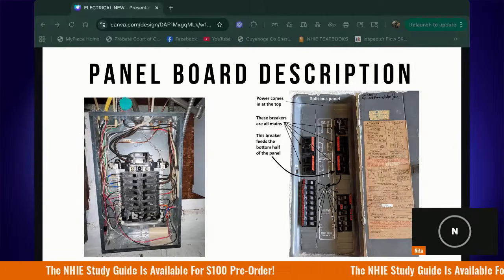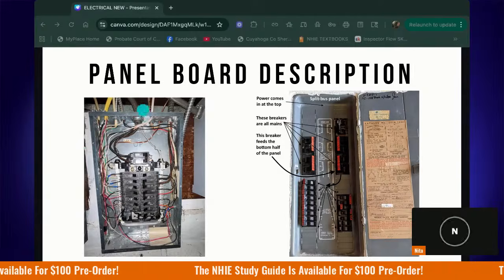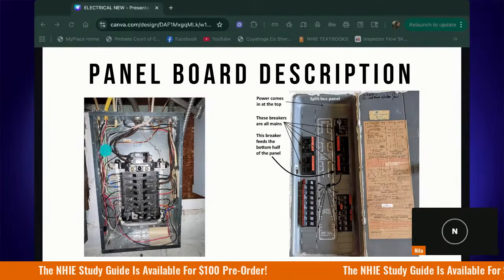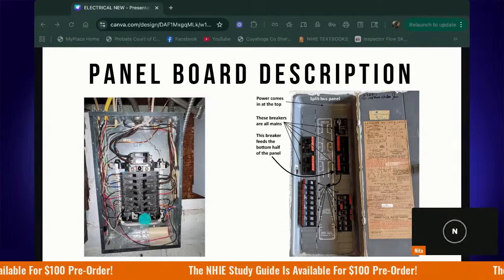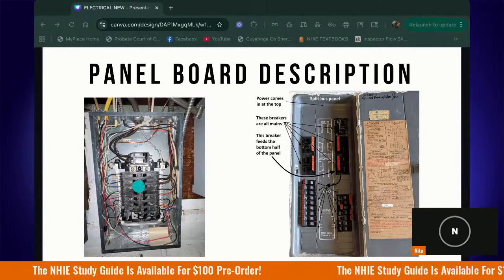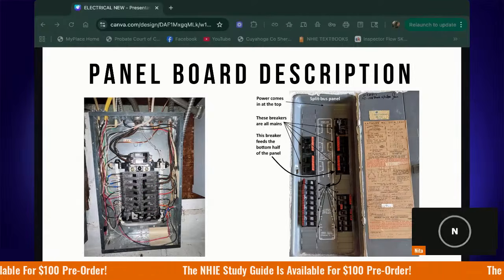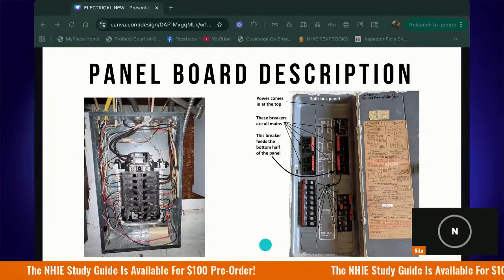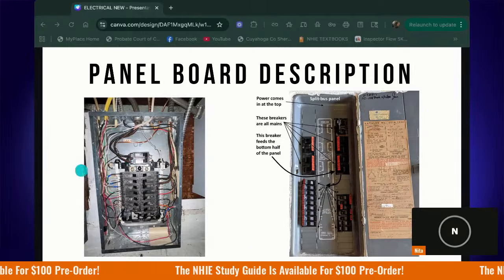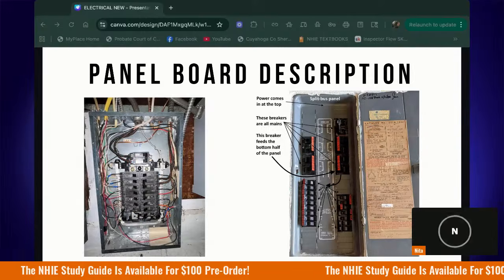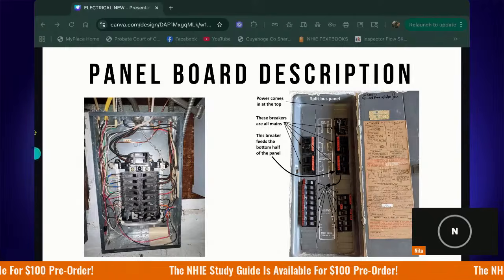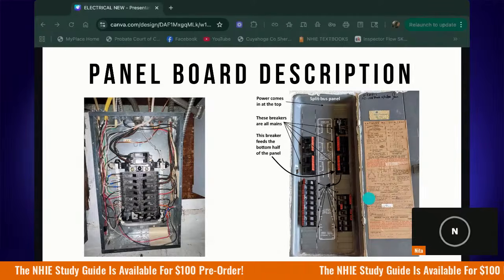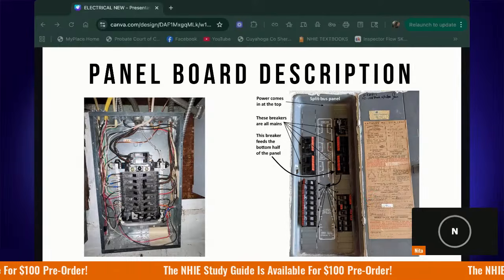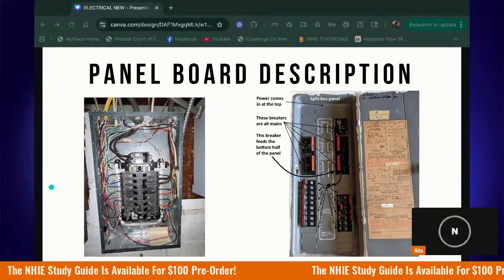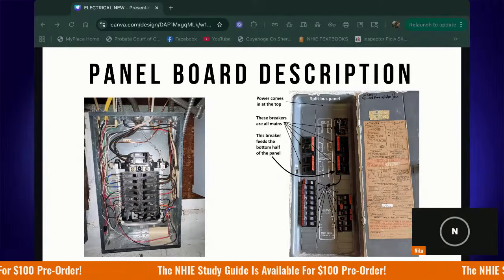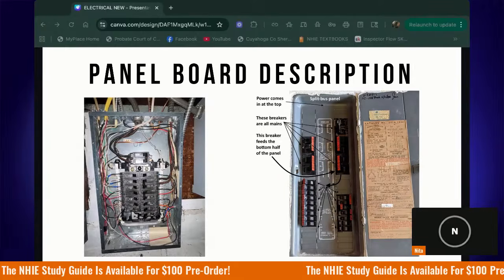So with the main breaker, you have your power flowing through. So this is our 2 hots and a neutral coming in from outside. The power is flowing through the main breaker down to your bus bars. And then you have, these are again your branch circuits here that are protected by the breakers. And then you have your main lug. A main lug panel board again is receiving, I said main lug for enclosure, I meant a main lug panel board. It receives its electricity from feeder conductors coming from another panel. So these are your sub panels. Okay, they are downstream, or they come after your service equipment or your main panel.